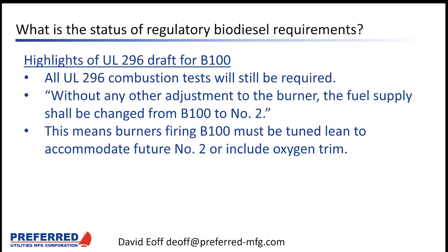Then there's a big requirement that's new, and I quoted it here. "Without any adjustment to the burner, the fuel supply shall be changed from B100 to number 2." Because biodiesel has fewer BTUs per gallon than diesel, this means burners firing B100 must either be tuned lean to accommodate future number 2 oil, or include a feature that can automatically compensate, like O2 trim. This is actually really smart on the part of UL, because it anticipates the situation where a burner tuned on B100 needs to be switched to burning regular diesel in the event the facility can't get a delivery of B100. And for the foreseeable future, B100 is going to be much less common and less available than ultra low sulfur diesel.